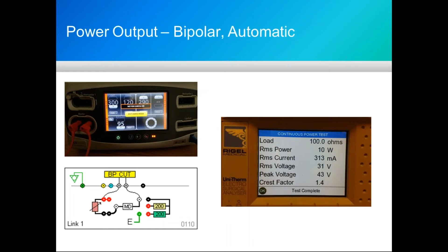For bipolar, you're going to have 100 ohms, and you're going to go through these 3 settings. For 95 watts, you'll look for the mA output. And on the previous screen, you'll be able to see where the mA is. And this will go on regardless of your testing device.